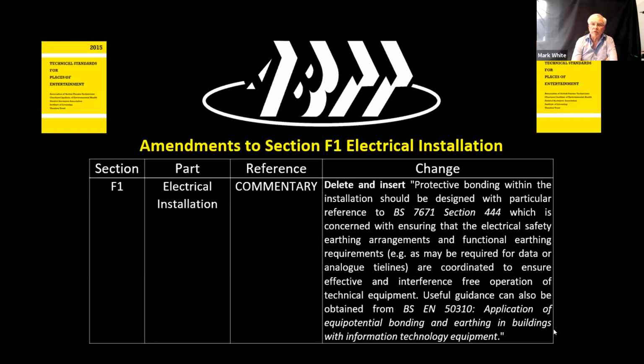So you used to have everything going back to a separate earthing system, back to the main earthing conductor. These technical earths were often in cream cable. Now our wiring regulations have changed and we can't do that anymore. The best practice for this is to use the same sort of earthing that we use in IT equipment, which basically means everything is solidly earthed as it needs to be. This is what's going to happen anyway.